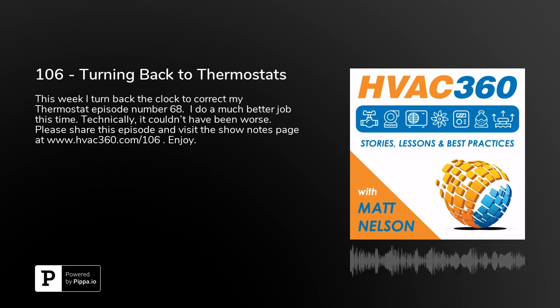Now the thing about it is, these thermostats on the wall have a couple different functions, and I didn't really necessarily go into that in my previous podcast. But the one thing I wanted to cover was that there's a set point and then there's an offset, and you've got to think about it. You have to go through it with the temperature controls just so you understand exactly what's happening, because there can be a set point. You go up to a thermostat and say, okay, I want a set point of 70 degrees. Now, when you do that with a self-contained unit, that 70 degrees is a line in the sand. It is going to turn on or turn off based on 70 degrees.